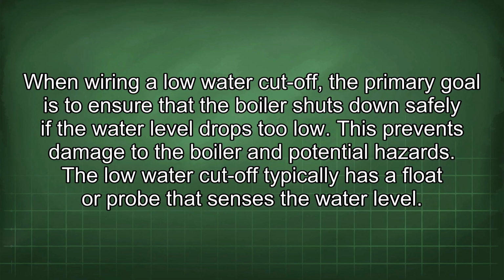When wiring a low water cutoff, the primary goal is to ensure that the boiler shuts down safely if the water level drops too low. This prevents damage to the boiler and potential hazards. The low water cutoff typically has a float or probe that senses the water level.